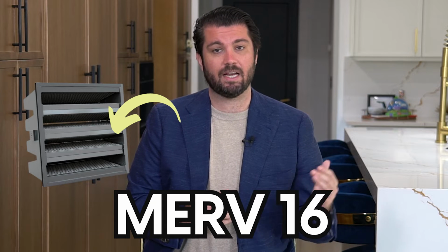This particular product, the reason why I like it so much, was developed in about 2017, and since then it has been able to successfully remove particles as small as 7 nanometers in size. That's very, very tiny, the size of some viruses. It's a MERV 16 rated filter, which is 95% efficiency, and it only causes the pressure drop of a MERV 8, which is really important for HVAC nerds, because if you install too good of a filter, it restricts too much airflow.